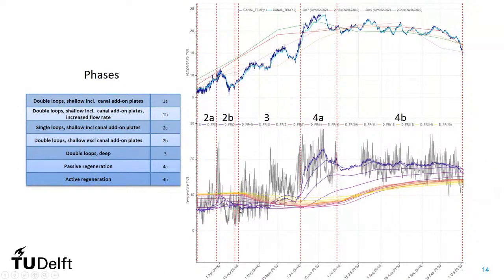What you can see afterwards is the end of the water measurement period, at the end of phase 3, which is when we first use the deep activation, so when we first go into the soil. What you can see here are all of the ground temperatures, sequentially through the ground, from purple being the most shallow to yellow being the most deep. There's a significant deepening of the lowering of the temperature as we extract heat from the ground.